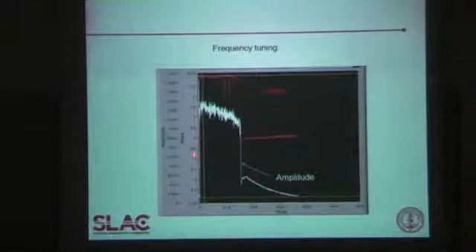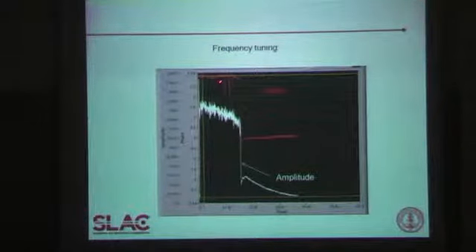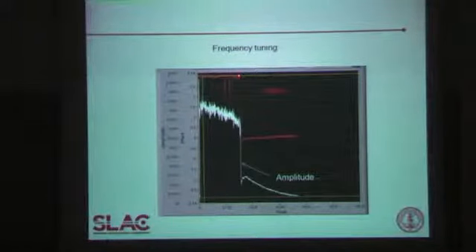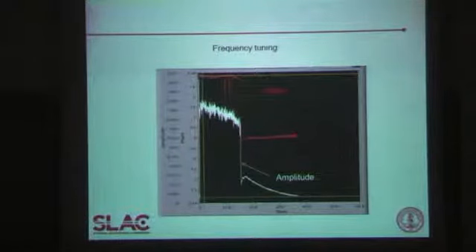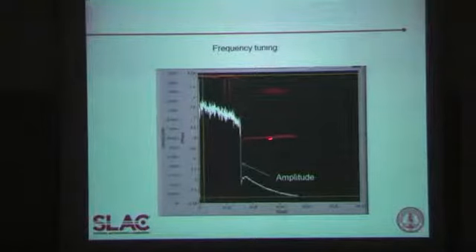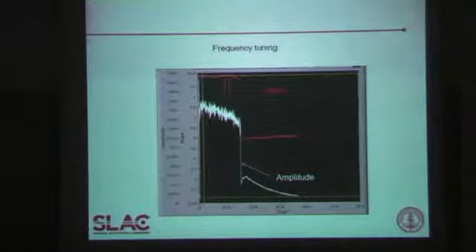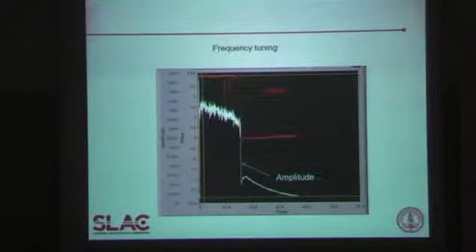This is a typical reflection that comes back from the cavity. It shows the phase and the amplitude — this is the phase of the cavity after adjustment. The RF pulse ends here, and when it ends the cavity starts to emit at its normal resonant frequency. That emission at the resonant frequency is mixed back with the original signal being sent to the cavity, and if that turns out to be a straight line, it means the cavity is exactly on frequency.